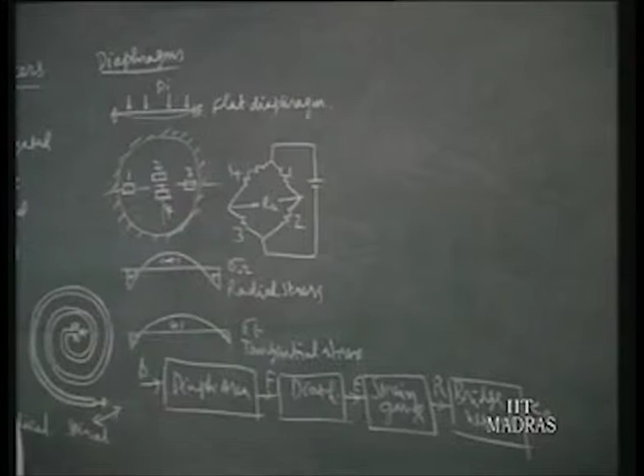1 and 3 will pick up the compressive strains. 2 and 4 will pick up the tensile strain. So this is 1, 2, 3, 4. 1 and 3 compressive, 2 and 4 tensile. So this gives the maximum sensitivity for the bridge network. So the epsilon strain produced is picked up by the strain gauge, and R is changed. So resistance of the strain gauge is changed. Then we get an output from the bridge network.